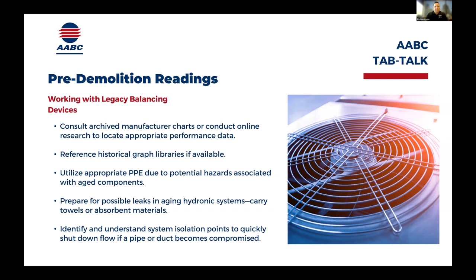One thing we brought up, some challenges to look at when dealing with hydronic flows in pre-balance readings, has to do with age of systems. As we see these older systems, depending on the materials used for install of the piping, there may be corrosion and buildup. So we have to be very careful when taking those readings to understand there may be things happening inside that pipe or hydronic system that we cannot see.